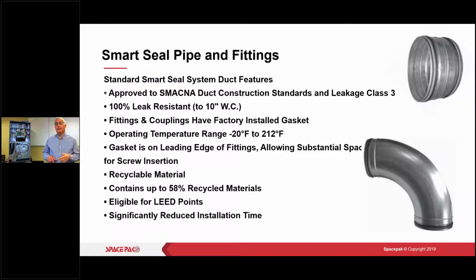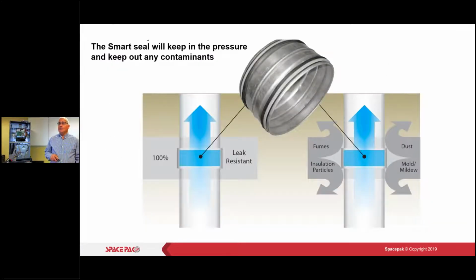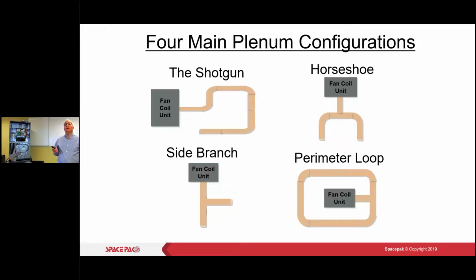I don't have to worry about leaks. A lot of older systems we see have leaks. You see a lot of duct tape that over the years eventually starts to peel off. All right. Not good connections where the 2-inch drops came. We're leaking air all the time, and the homeowner isn't quite pleased with the system. So you want to make sure you're using this type of product. It's really going to work quite well. All right, so again, I'm calling out the gasket because this really makes a huge difference here. It keeps contaminants out and keeps the pressure high in the plenum. So we can use any type of configuration we want. These are the most common ones we see when we run our system.